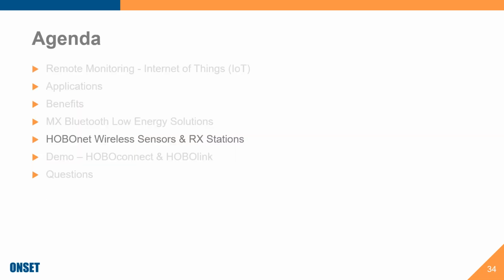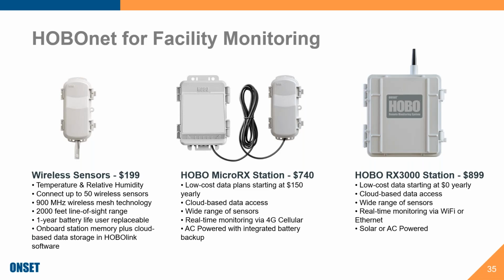Taking a look at the HOBOnet system, this system's a little different where it runs on the 900 megahertz. It is a mesh network. You can connect up to 50 sensors per station. We've seen it, we've spec'd it outside at 2,000 feet line of sight. I've personally seen this go through 3 floors that were made out of 18 inches of cement and communicate fine. They do have a 1-year battery life.